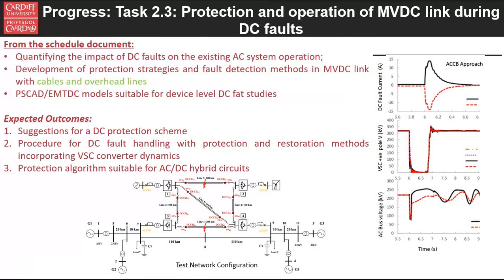Yeah, the protection and operation. This work is taken by Tibin, and the protection is on the DC. Say if the system is subject to a DC fault, as Karen and Norman mentioned, because you can see the cable and overhead line, they could be subject not only to permanent fault on the cable, but also some transient lightning on the overhead line.